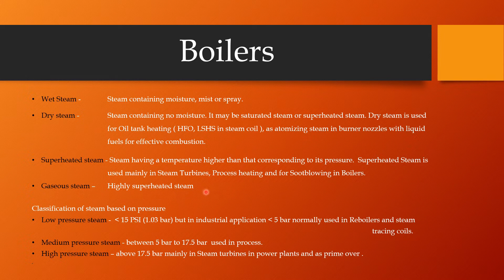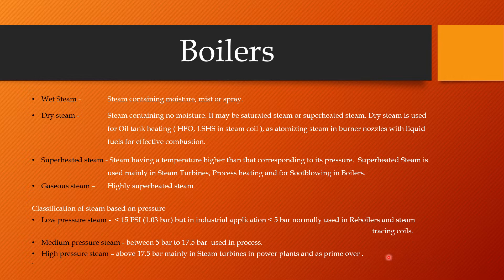Gaseous steam is highly superheated steam and is also used in power plants and steam turbines. Further, steam is classified based on pressure. Low pressure steam is less than 15 psi or 1.03 bar; in industrial applications it is generally considered less than 5 bar, and is used in re-boilers and steam coils. Medium pressure is between 5 bar and 15 bar, used in process applications. High pressure steam is above 15 bar, mainly used in steam turbines, power plants, as a prime mover in place of motors, and in processes requiring superheated steam at high pressure.